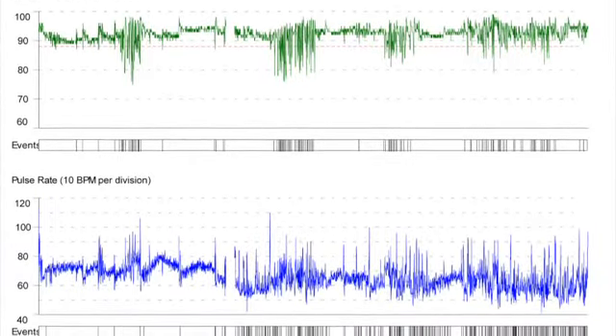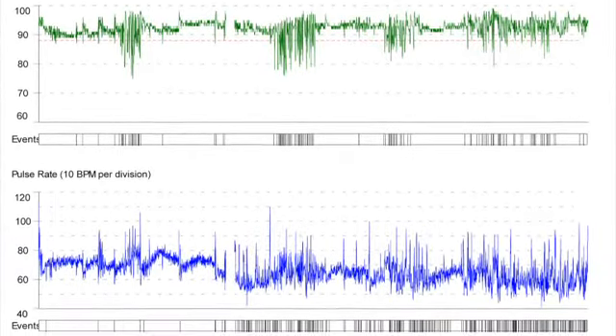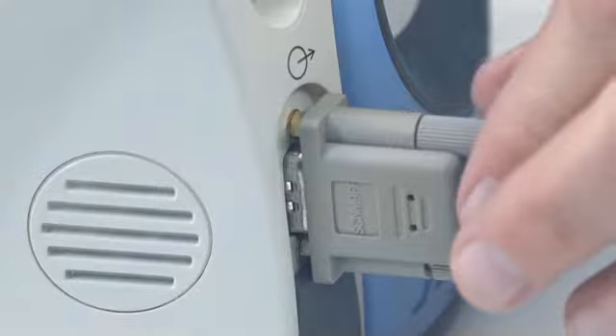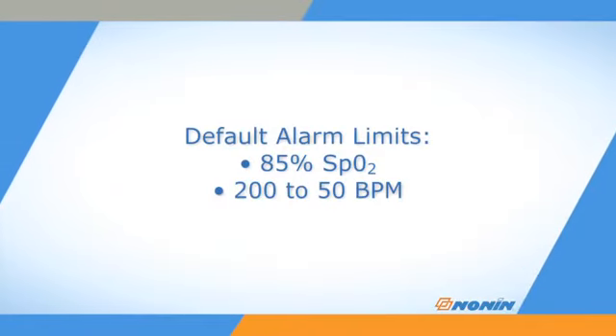The Avant 9600 stores at least 115 hours of continuous arterial oxygen saturation and pulse rate data. This data can be transferred and analyzed in Nonin's nVision software via a modem cable from the oximeter to a computer with nVision installed. The Avant 9600 oximeter comes with a default low alarm setting of 85% SpO2, a high pulse rate of 200 beats per minute, and a low pulse rate of 50 beats per minute.